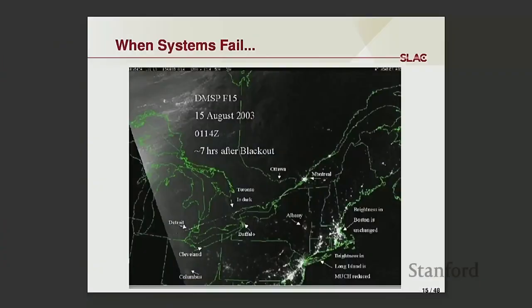So if you have extra power, it's much easier to cut down and make up for the shortfall, and that's what happened. Long Island was still recovering from the event even 7 hours after. These are major events, and massive damages were incurred by many people and organizations. So systems can fail - by the way, this event was initiated by a tree falling on a line near Cleveland, so obviously very far away places were affected by an event like that.